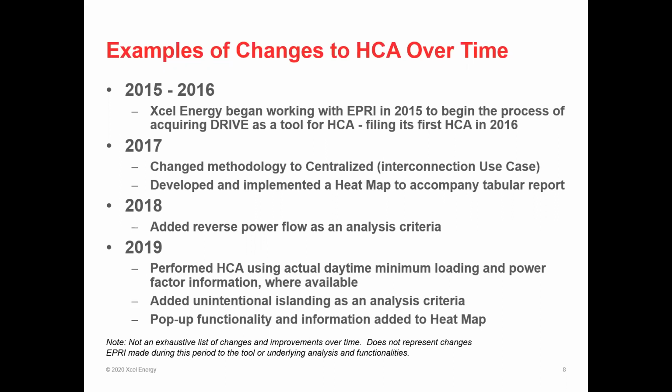We also developed and implemented the heat map to accompany our tabular report. In 2018, we added the reverse power flows analysis criteria, and in 2019, performed hosting capacity analysis with actual daytime minimum loading and power factor information where it was available in our system. We also added unintentional islanding as an analysis criteria and included the pop-up functionality with its added information to the heat map.